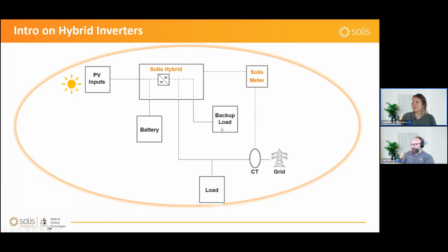AC backup, AC grid port, where you can connect your critical loads, your backup loads, and these will be supplied power from the battery and from the PV in case the grid goes off. But otherwise, in normal, let's say we call it self-use conditions, when you have a grid connected and you have PV that is being generated, well, normally if that PV is not consumed locally, it would go out to the grid.